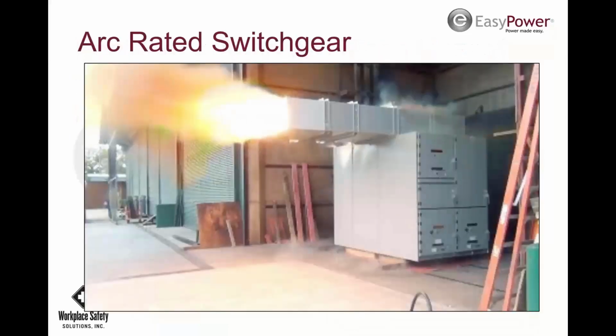Arc flash relays, arc flash switchgear, arc rated switchgear. This is very expensive, but you notice how this is real heavy steel, bolted, with bolts real close together. So this stuff can handle the fault, the actual arc flash itself. A lot of times they'll set this up so that it vents outside the building somewhere in a fenced-in area, coming downward toward the ground. The problem then is you have to make sure and keep people away.